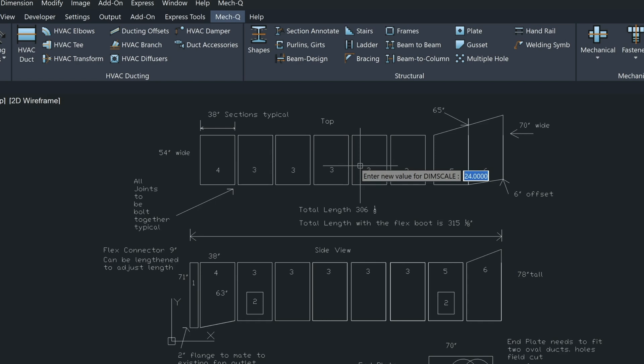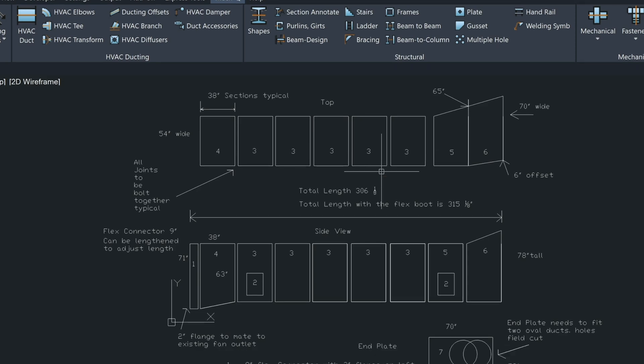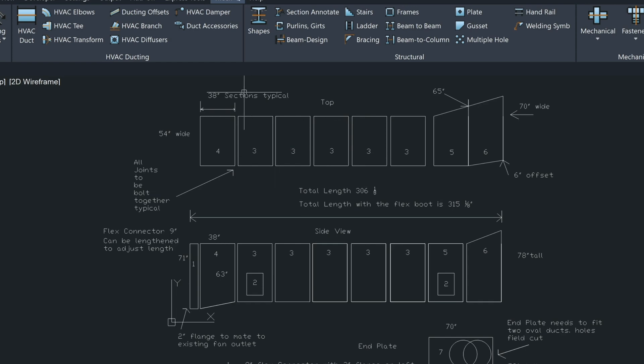So if you're going to plot this out at half inch, if you wanted to plot it out at quarter inch you go to 48. Eighth inch is 96. This dim scale is important with Mech-Q because Mech-Q uses the dim scale to factor the heights. And I'll be turning the option on where it will annotate the duct as we go.